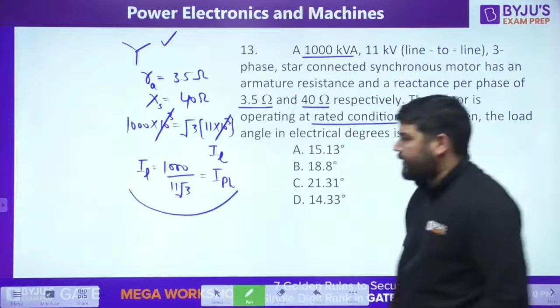The machine is operating at unity power factor. If you draw the machine diagram, this is my terminal voltage VT, here is the resistance and reactance, and this is my internal voltage EF. Let's assume this voltage is at 0 degree, with the rated phase current also at an angle of 0 degree. VT is the phase voltage, 11 by root 3. This is my phase voltage.